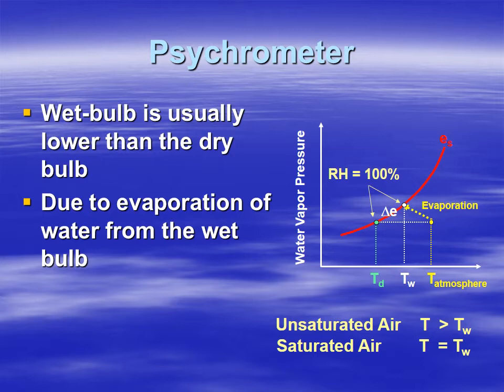When using the psychrometer, we wet the muslin wick on the wet bulb and allow it to evaporate. Through evaporation, temperature decreases because it takes energy to convert the liquid water in the wick into vapor — that energy comes from the thermometer and the surrounding air. At the same time, water vapor is being added to the air, so the yellow arrow moves left representing lower temperature, while water vapor pressure increases, moving up at an angle toward the red saturation line.